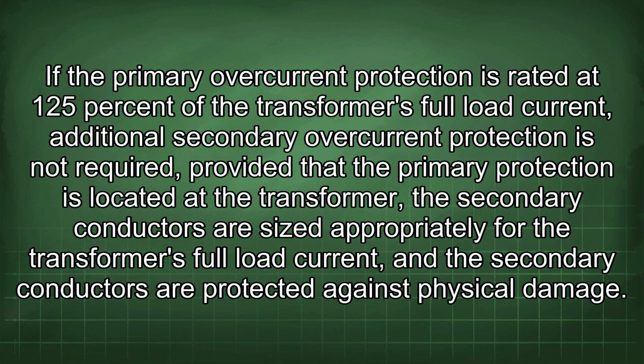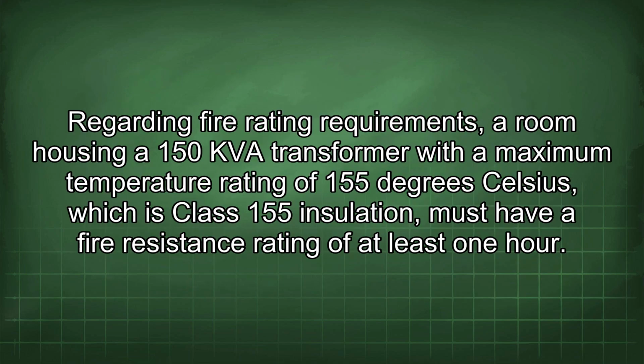If the primary overcurrent protection is rated at 125% of the transformer's full load current, additional secondary overcurrent protection is not required, provided that the primary protection is located at the transformer. The secondary conductors are sized appropriately for the transformer's full load current, and the secondary conductors are protected against physical damage. Regarding fire rating requirements, a room housing a 150 kVA transformer with a maximum temperature rating of 155 degrees Celsius, which is class 155 insulation, must have a fire resistance rating of at least 1 hour.